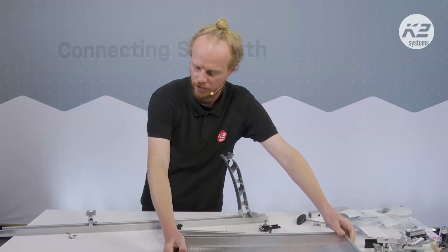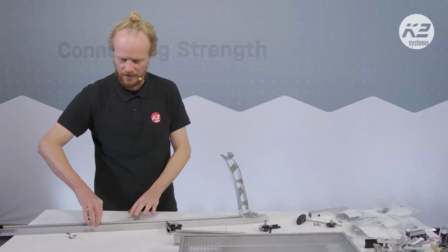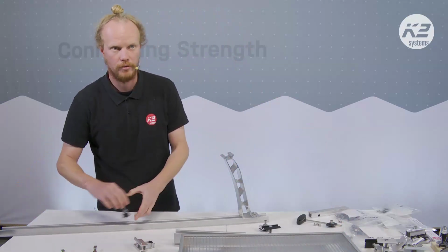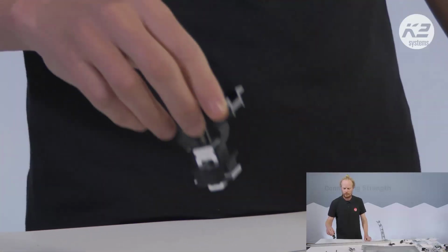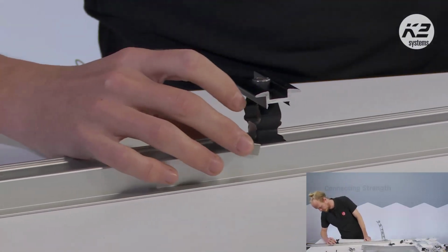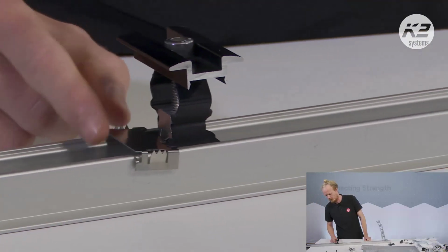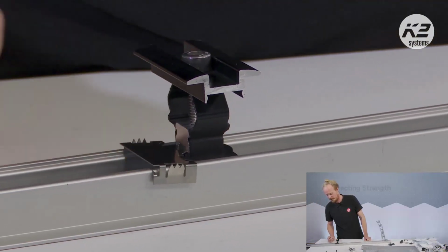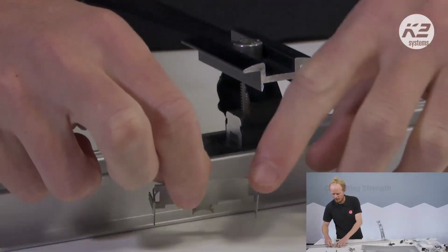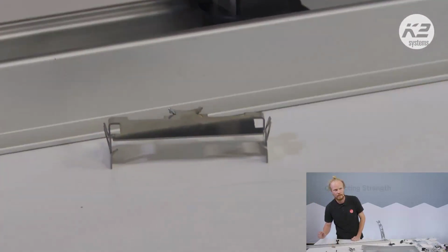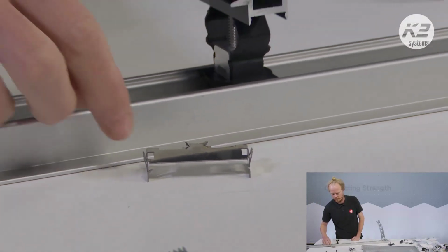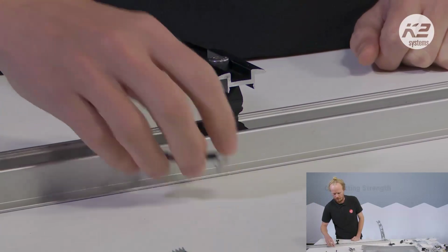For the different clamps and the different situations, we have slightly different products. So let's take that one out. For our new MK2 clamps, I'll just put that in the rail. We have a different pitch groove which acts on effectively the same principle. There are little teeth on it, working on slightly different sides. In this one, you can see the teeth are on the outside of the rail rather than on the inside. Again, as you tighten, they're just going to scratch into the rail, and these ones up here will scratch into the module.